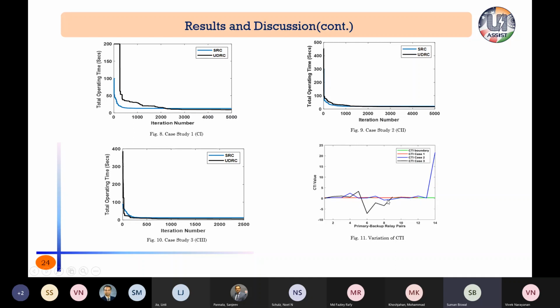But if the same setting is applied to islanding or grid connected mode, the performance gets worsened. As it is seen for the black curve, the CTI becomes negative. It signifies that the backup relay operates faster compared to the primary relay. So this is what we don't want. So if we change the topology of the system, the settings of the relay also need to be changed. Otherwise, the performance of the system will get hampered.